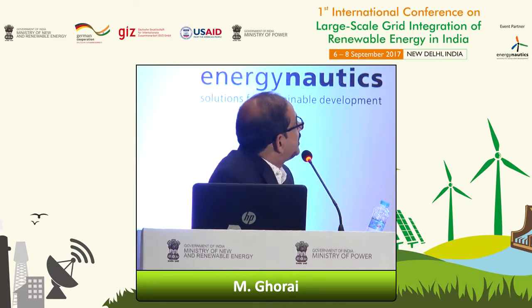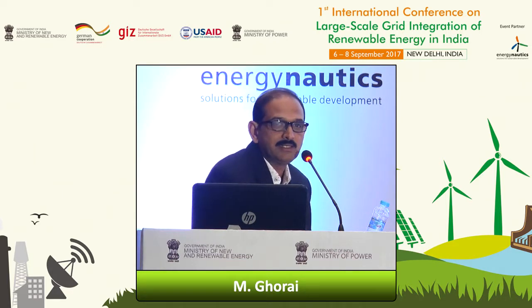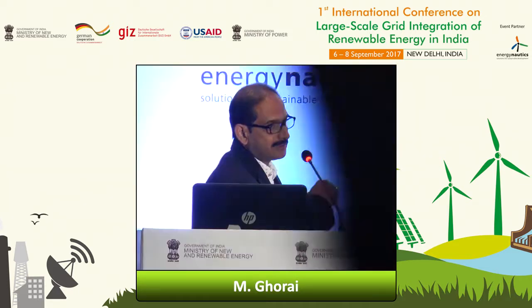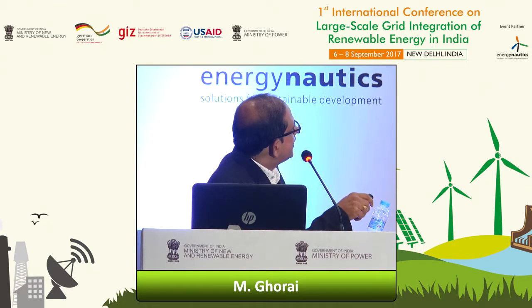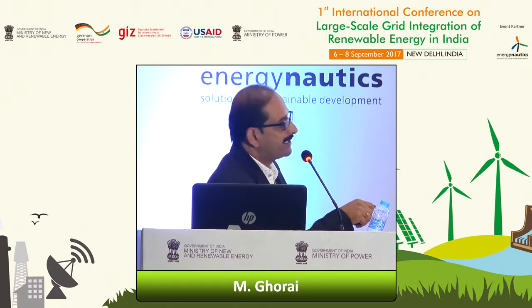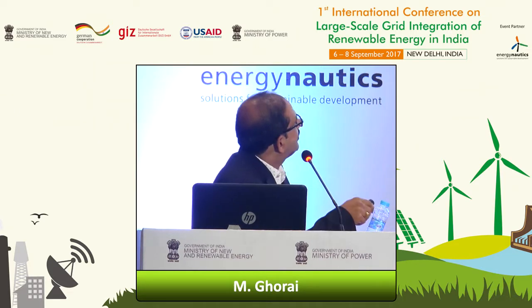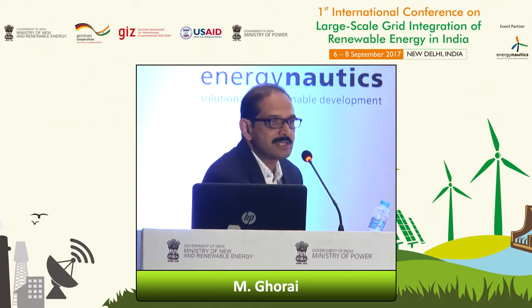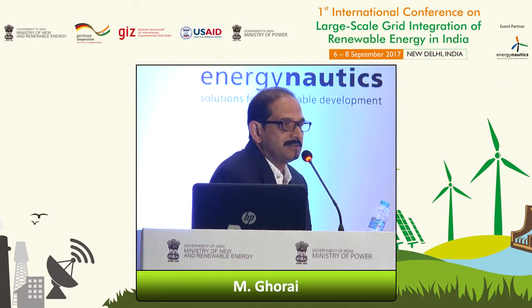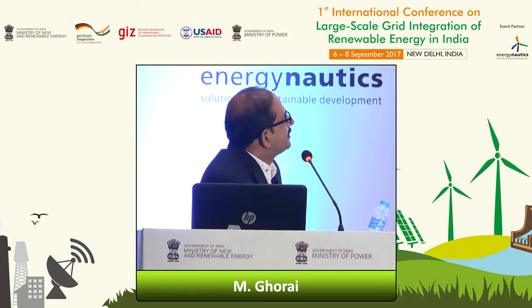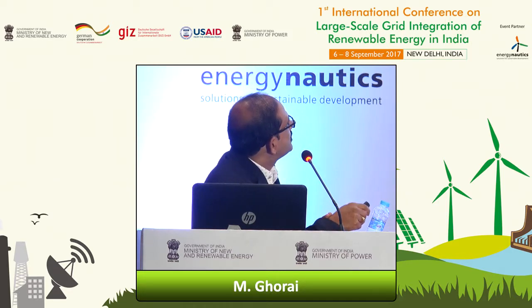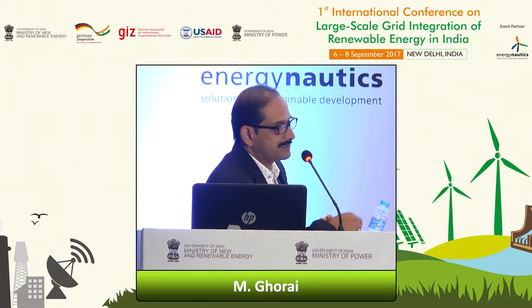This is the ride-through requirement. You must have seen the HVRT requirement of the grid code in my earlier slide. When such an event happens, the DVAR goes down. Red is the DVAR, so it goes down and then keeps the profile as per the grid code. The grid code says that if it is within that, the turbines are not allowed to trip. You can see that the wind farm output has remained the same, and it has not tripped.